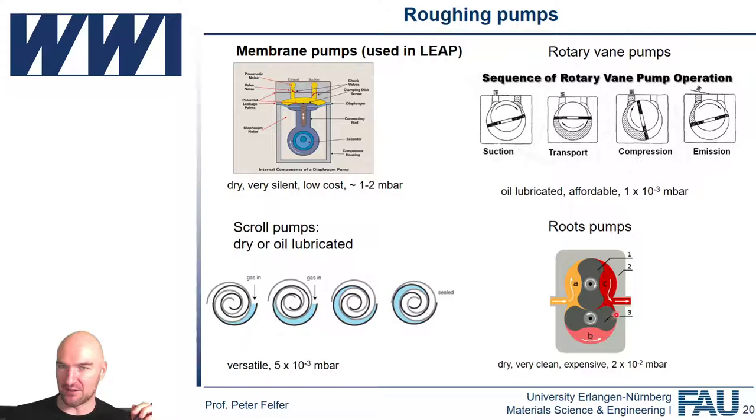But the biggest downside of the roots pumps is they're extremely, extremely loud. I've got a bunch of roots pumps in my lab, and my PhD students hate them, because if you're in a lab with a roots pump, you can essentially only sit there with earplugs, because they're extremely loud. If you have a separate room where you can put them far away, they're essentially probably the best pumps as backing pumps. But they're really loud.